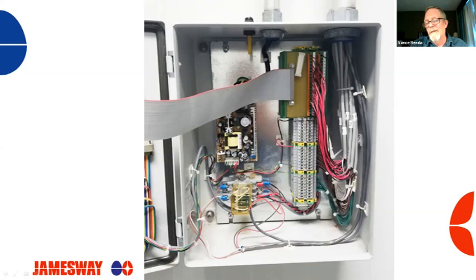Again, you could be hooking this to a horn, tone generators, strobe lights. There's several things we can do, but it's important that we use this relay to isolate anything you're doing external from this machine. The reason I want to point this out is we have 12 volt negative here, 12 volt positive here, and ground here. And I've had people try to use the power generated by this system to do things external to this system, and that's not good. This power supply's only function should be to drive your thermostats.